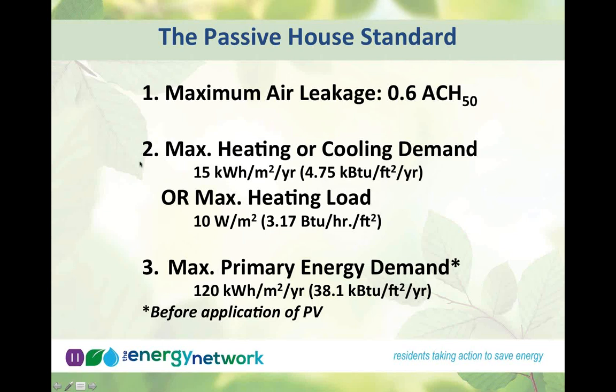Then there's a maximum heating or cooling demand, which is a measure of the amount of energy that must be added or removed over the course of the year to keep the building comfortable. This can also be met with the maximum heating load, and this is the peak power, basically the size of the heating system.